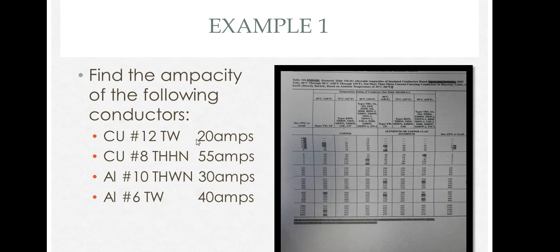In these examples, I'm only going to do one example. For copper number 12 TW, you go to the copper, you go to its size number 12, and the ampacity of a copper number 12 which has TW insulation is 20 amps.